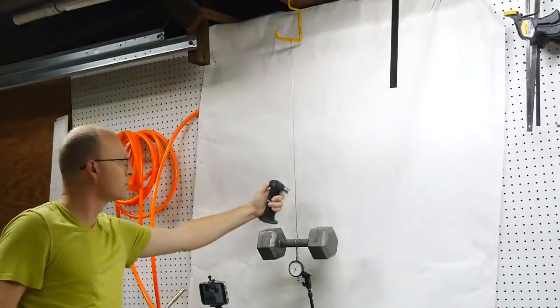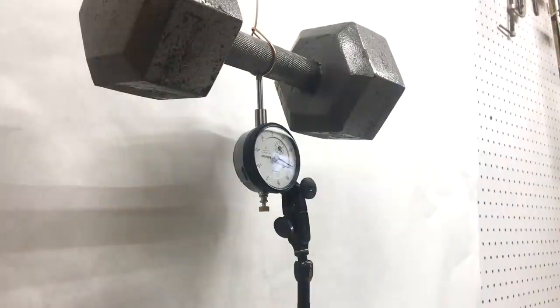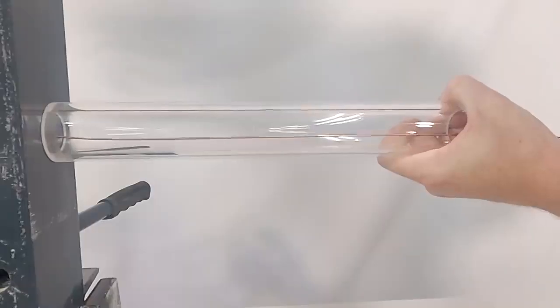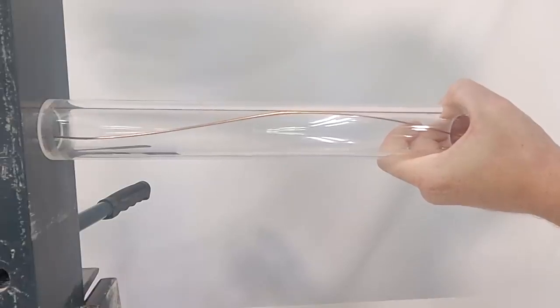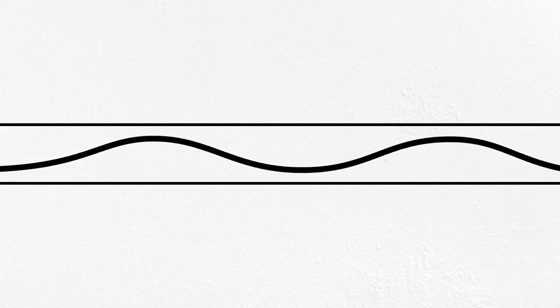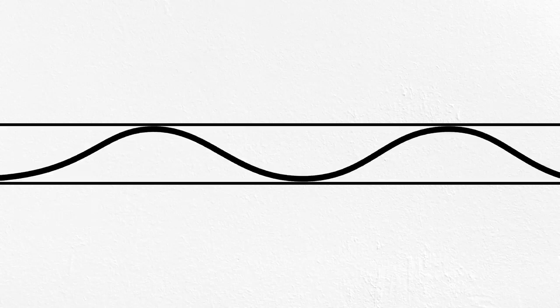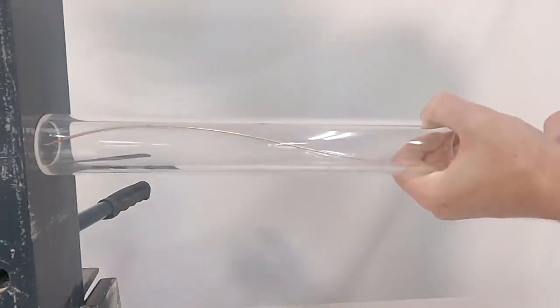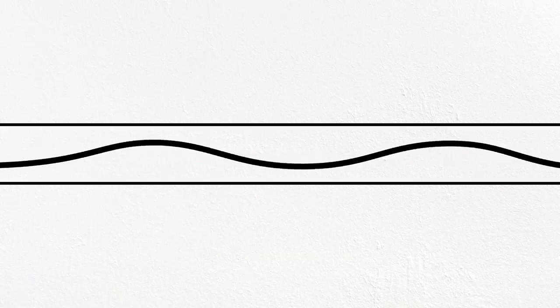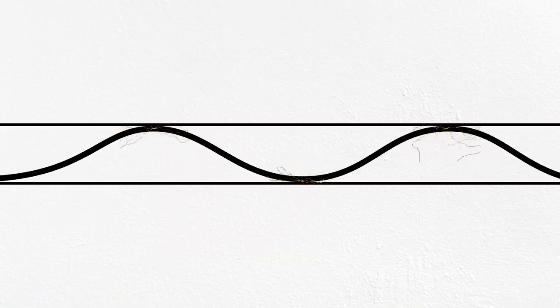When demands fluctuate, the current in a transmission line changes, and so the amount of heat in the line increases or decreases accordingly. As you might know, many materials expand or contract with changes in temperature, and that's true for the copper conductors used in underground transmission lines. When these lines expand within the outer pipe, they often move and flex in a process called thermal mechanical bending, or TMB. If not carefully designed, these bends can become tighter than the minimum bending radius of the cable, exceeding the allowable stresses within the material. Over hundreds or thousands of cycles of TMB, the paper insulation around each conductor can begin to soften or tear, eventually leading to a dielectric breakdown. In other words, arcs and short circuits.